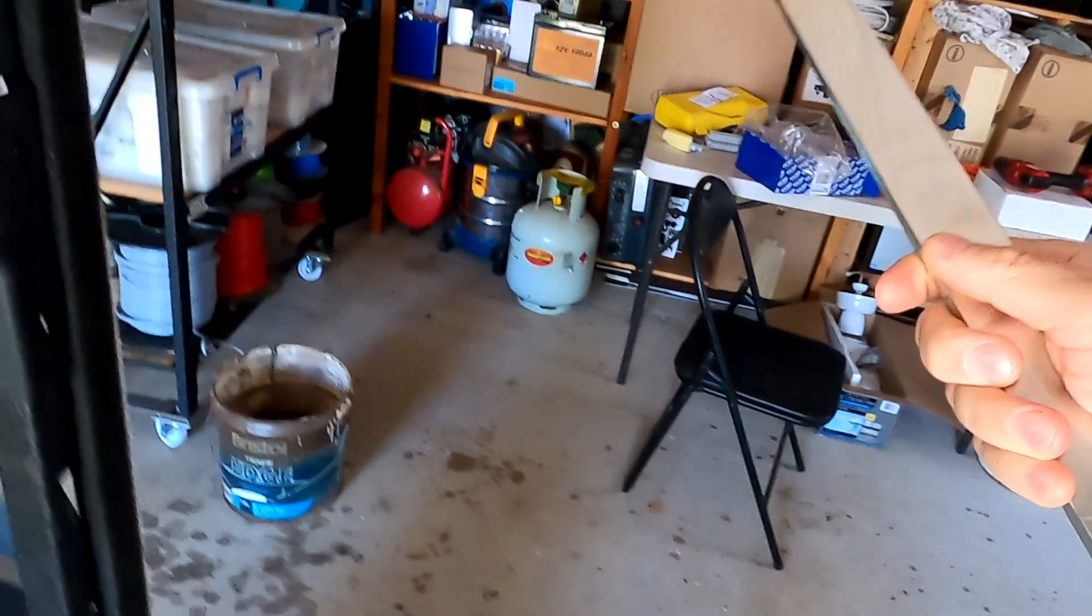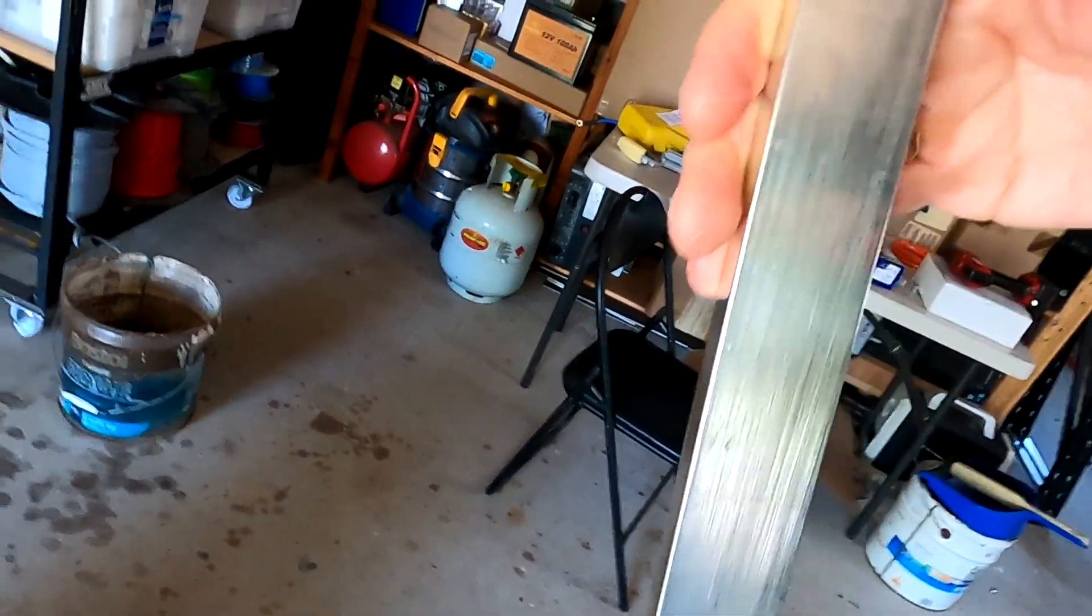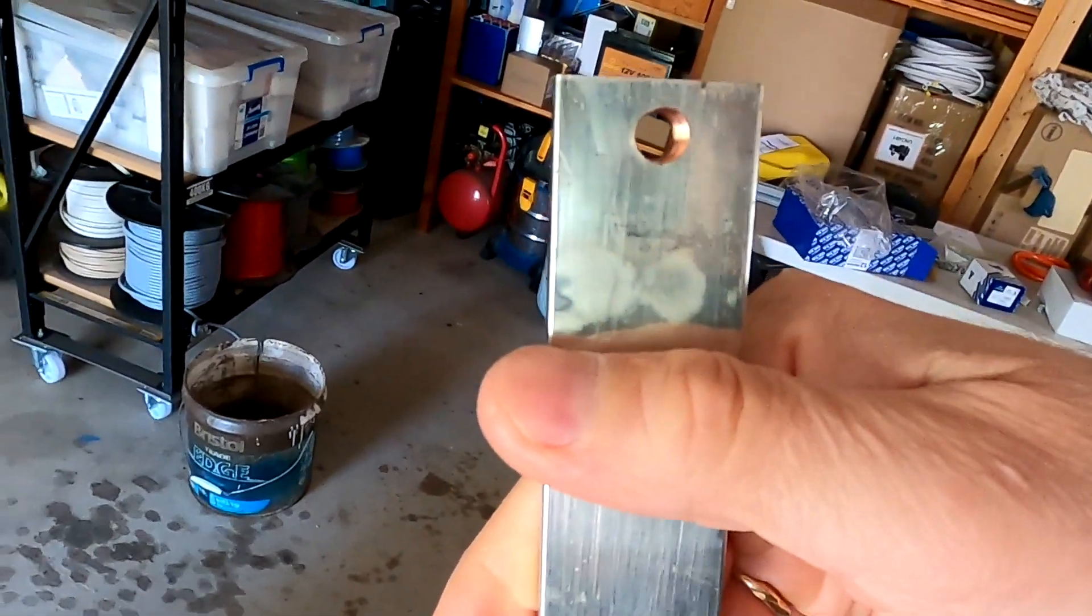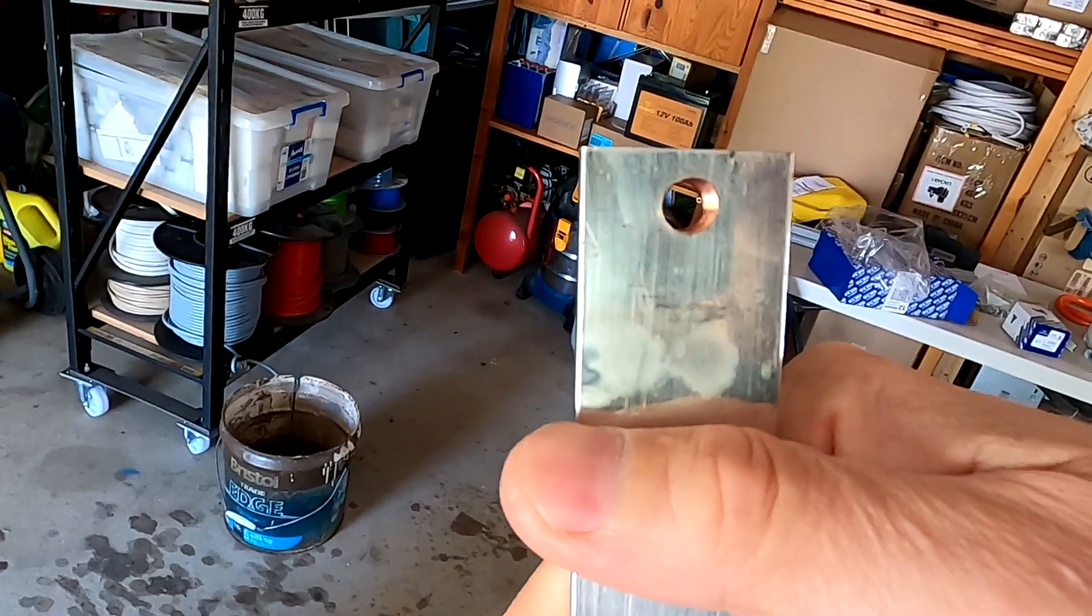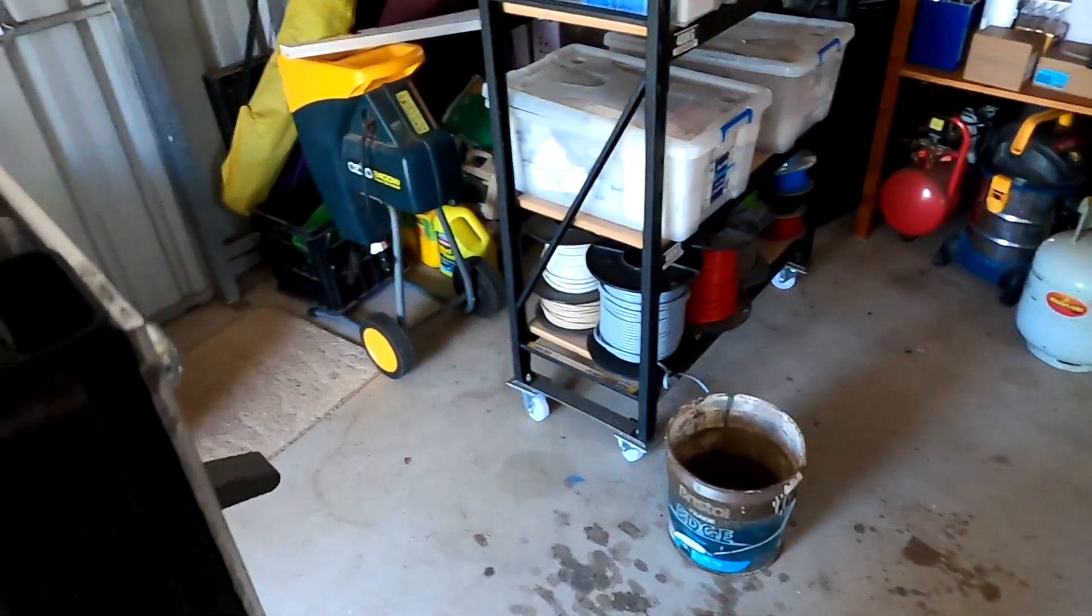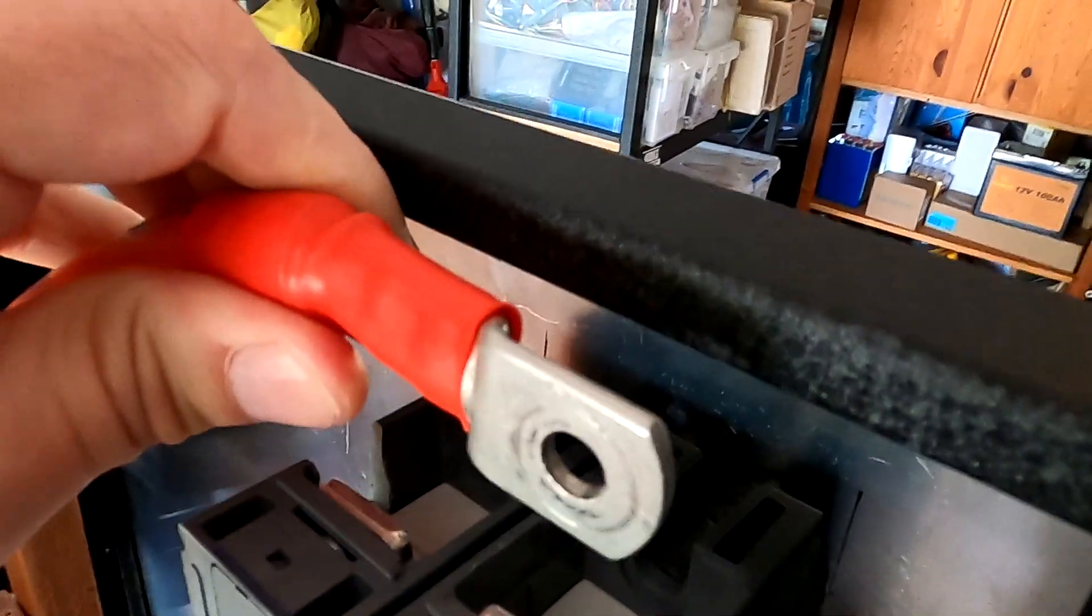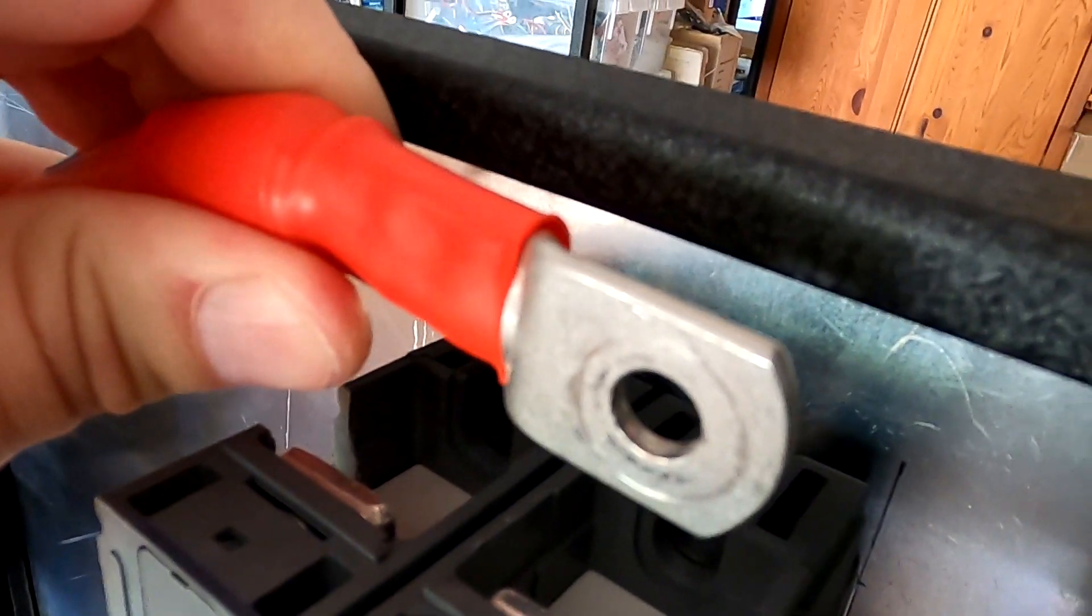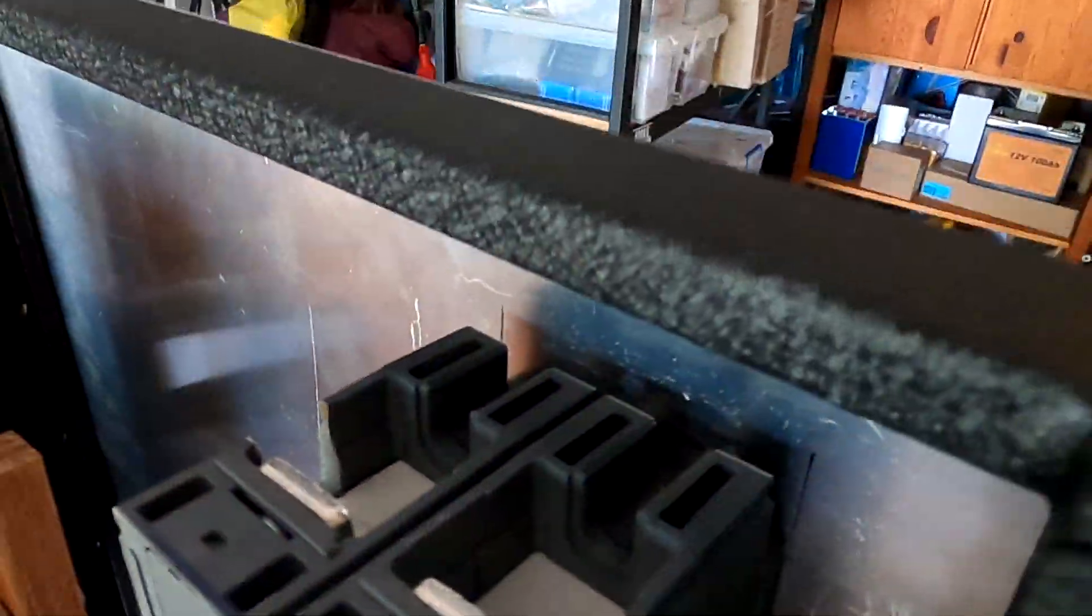I just have a little piece of bus bar maybe long like this, two holes in it. One hole connects to the screw here inside the terminal and the other one connects to my cable. Then the cable would connect to a bus bar which just sticks out and I've got my 90 degree angle there.